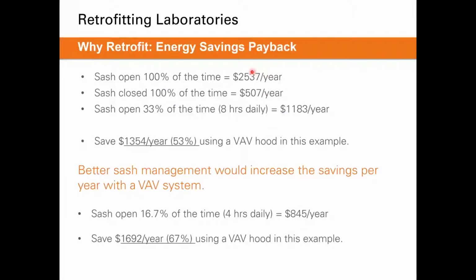So again, we went from $2,500 to $845, and that afforded us 67% savings by just reducing the sash open percentage time with a VAV hood. So you can see that 75% energy recovery that I mentioned a few slides before, that better sash management would drive this number closer to that.